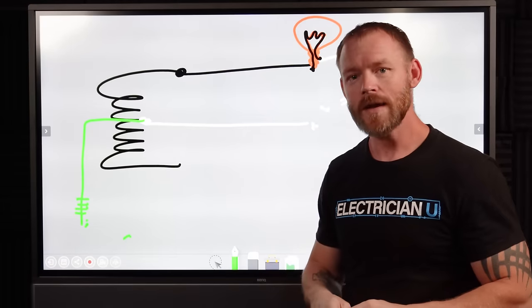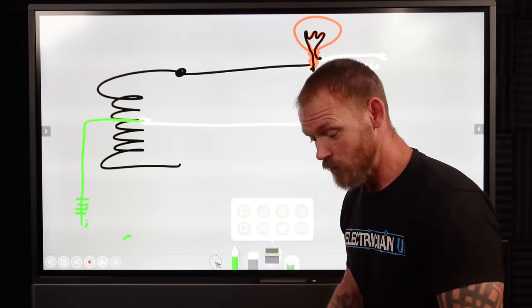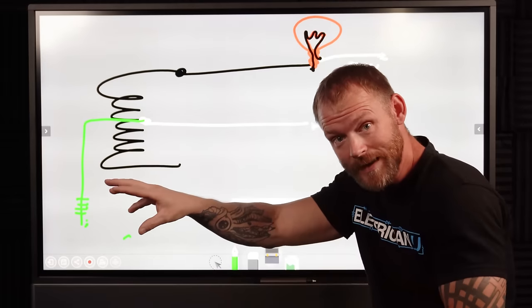But it's always, always, always between two points. So just always remember that. It can happen if you're kneeling on the ground and you're working on a light pole and you got your hand inside of a light pole. If your knee is wet, the earth is a conductor. If the earth is wet, especially if it's wet, you can introduce yourself to a circuit that way.